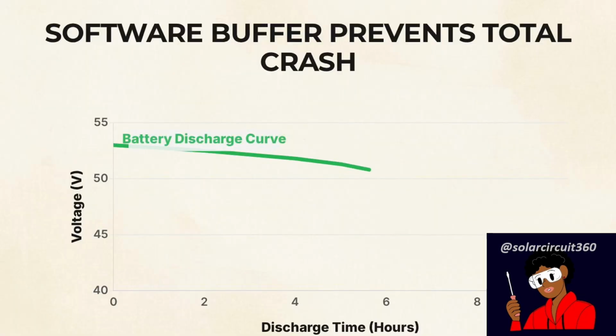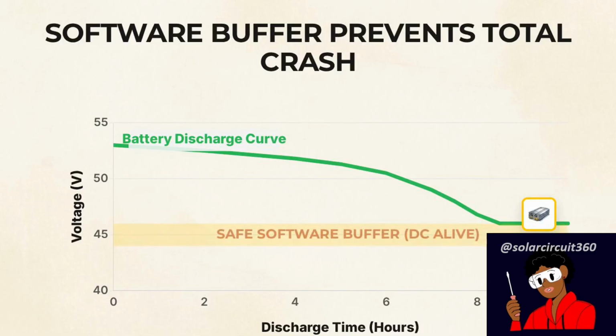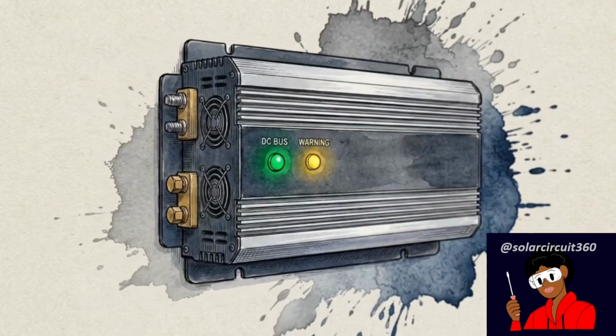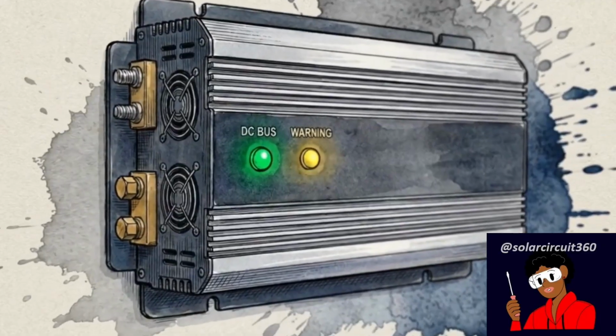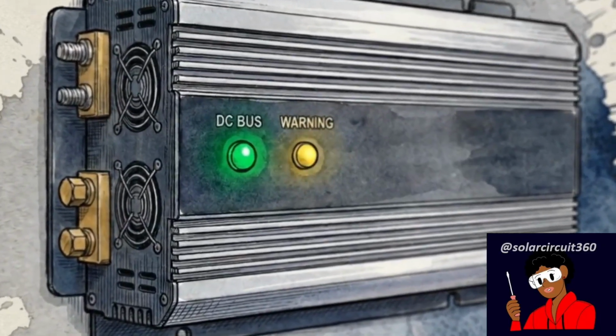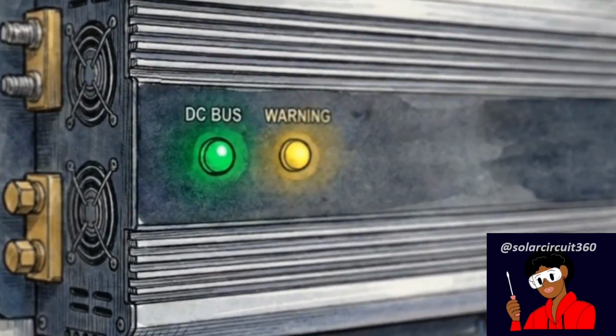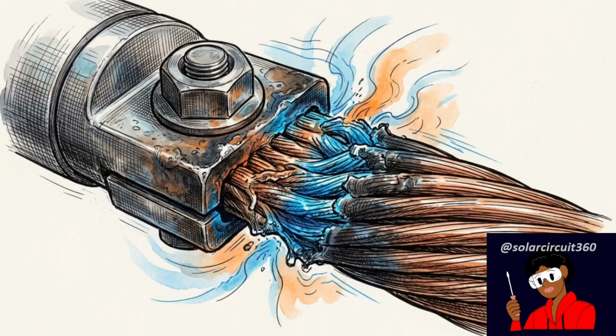Looking at the terminal drop on the chart, this red line is the absolute lowest voltage limit the hardware tolerates before cutting power. To prevent tripping, we set the inverter's low voltage disconnect above this threshold. During a safe shutdown sequence, the falling battery voltage hits that higher disconnect limit first. The inverter drops the alternating current loads, but keeps the DC connection alive. Programming this software buffer allows the inverter to gracefully manage a depleted battery. It sounds the alarms and preserves the DC bus for recovery, avoiding a total system crash.